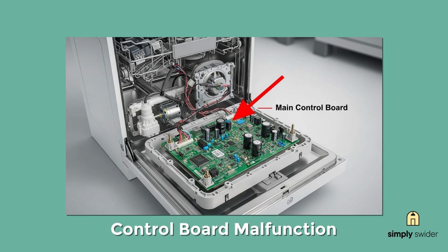When the control board starts acting up, it can throw E09 codes even when everything else is working fine. This happened to one of my regular customers. We replaced the heat pump, checked all the wiring, and that E09 just kept coming back. Turned out the relay on the main board that sends power to the heating element had failed.